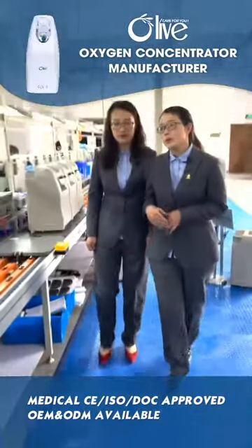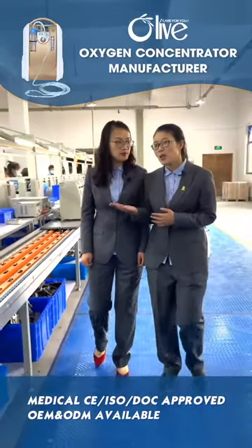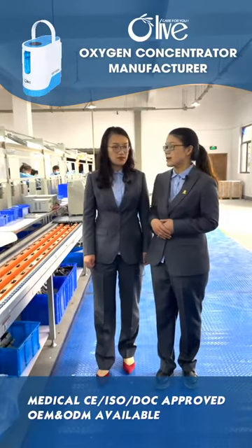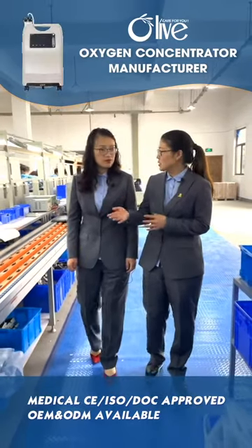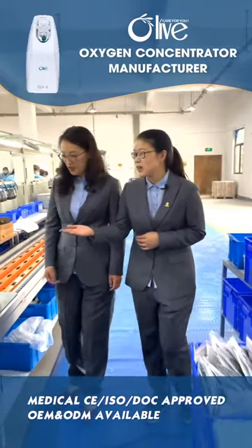And also, we should check the oxygen purity. Just as I told you, the medical oxygen concentrator must have high oxygen purity, more than 93%. So here you can check whether our oxygen concentrator is medical grade, up to 93% oxygen purity. You can try by yourself.